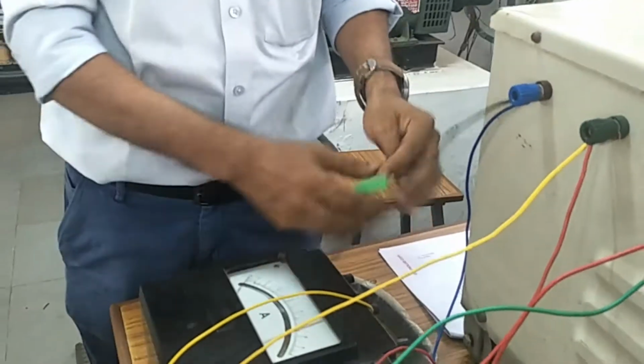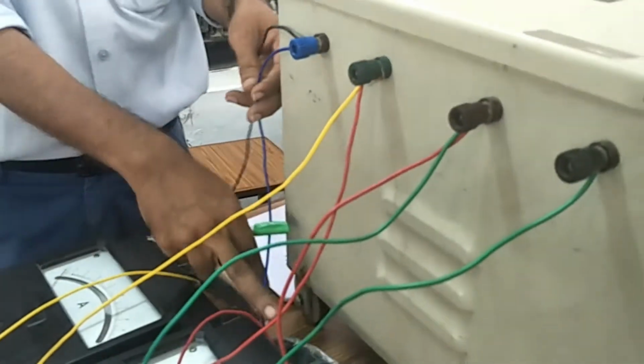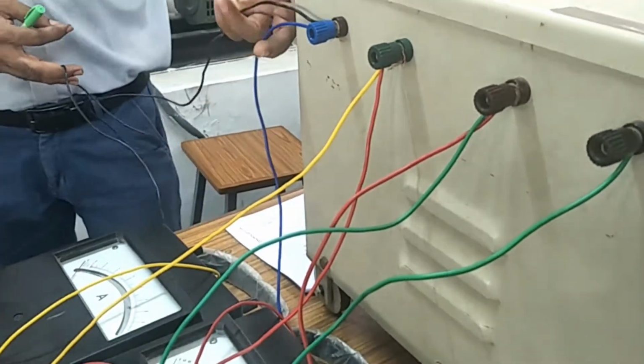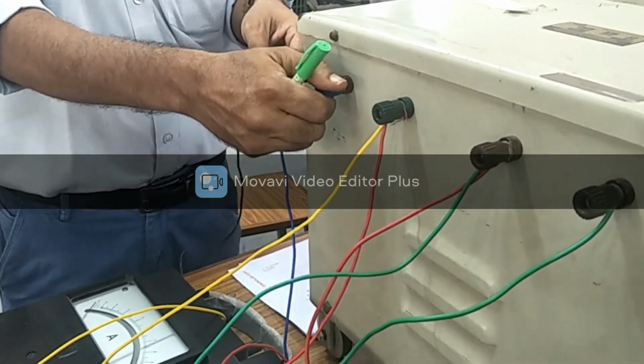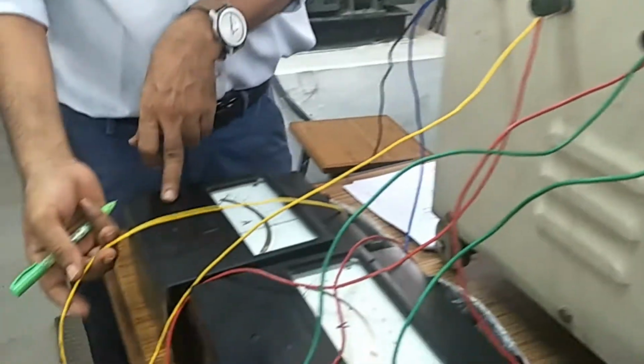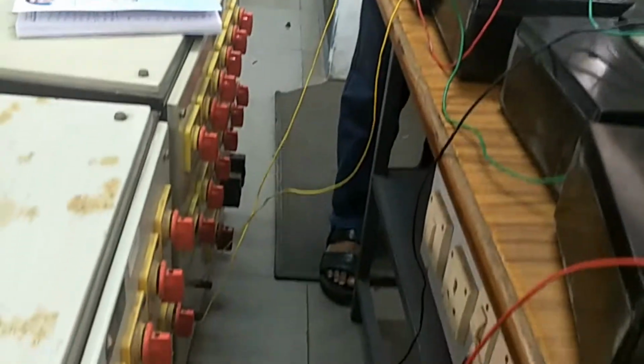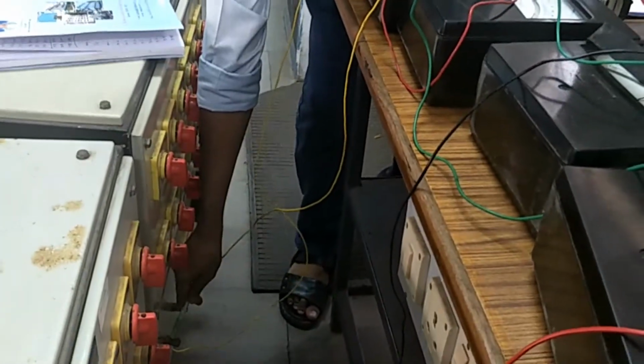Coming to the secondary side, please observe the voltmeter common and ammeter common. These two are connected to one terminal of the secondary. You can consider this as phase. And the ammeter's other end of the main transformer, secondary side, is connected to the load. See here, this is the load starting terminal. The load's other end terminal is connected to the neutral of the secondary. Similarly the voltmeter. So this is the secondary side of the main transformer circuit.